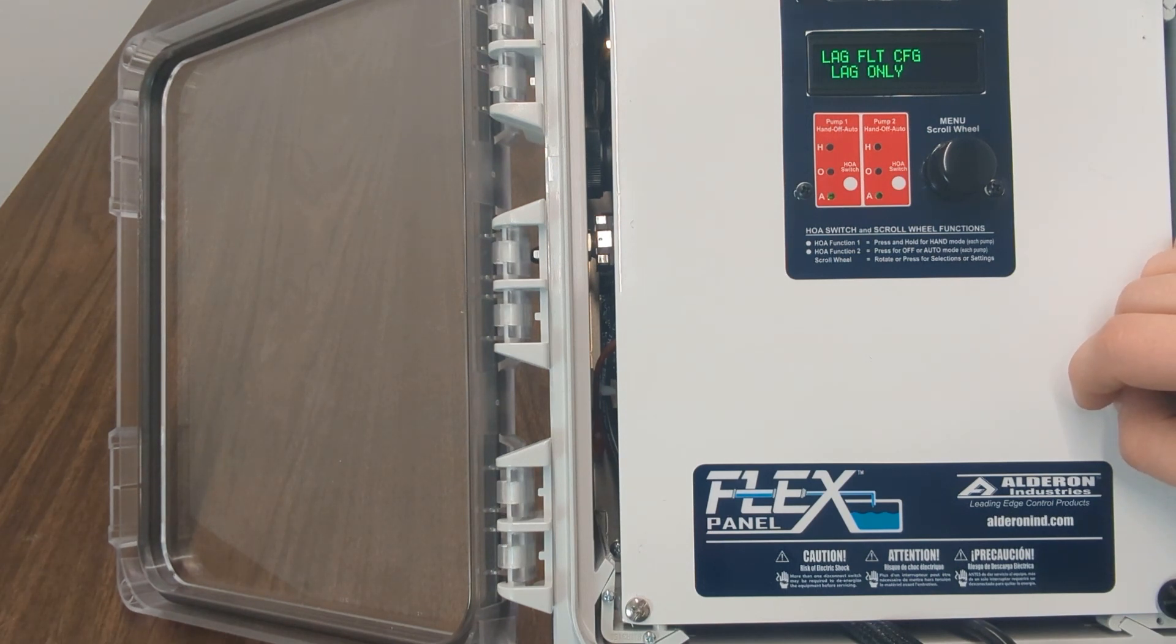After that, the system will ask lag float configuration. Click on lag only since on a four float system, we do not want to activate the alarm when the lag float activates the lag pump.